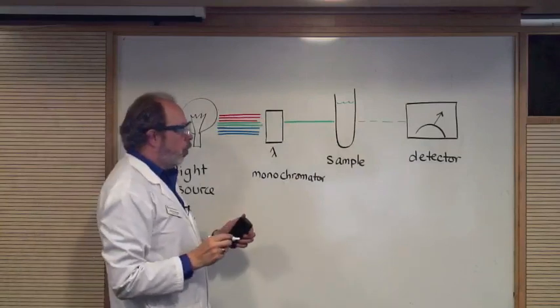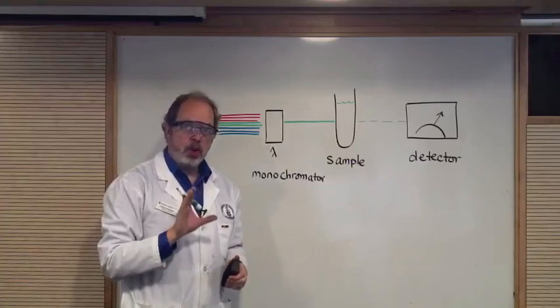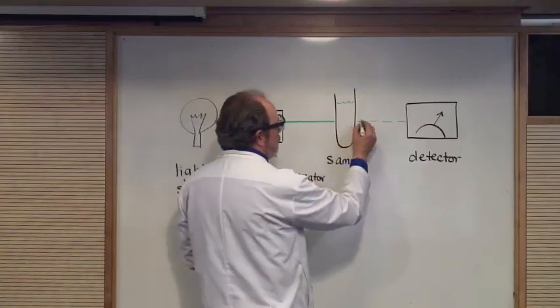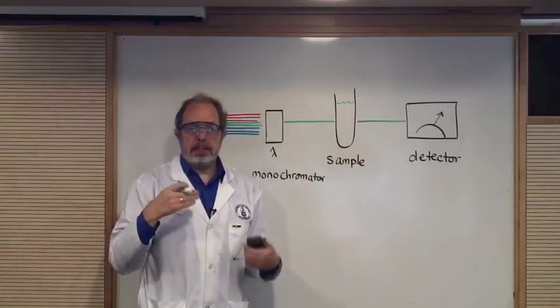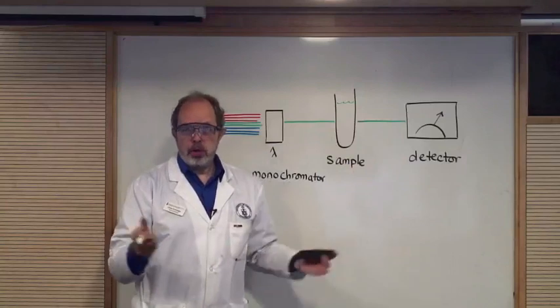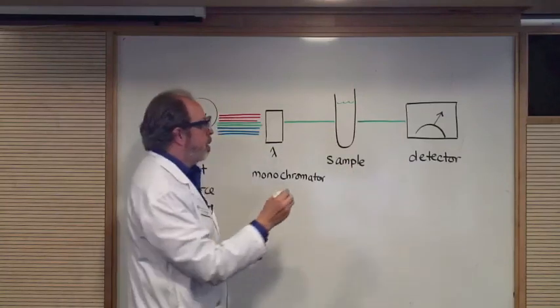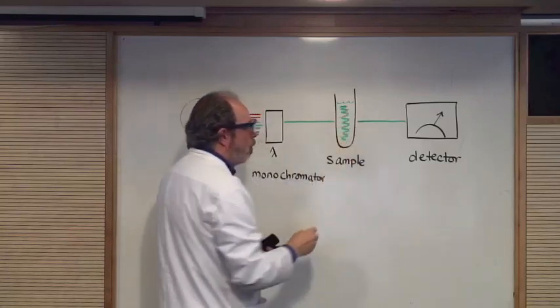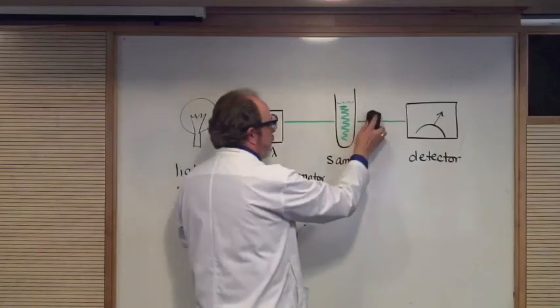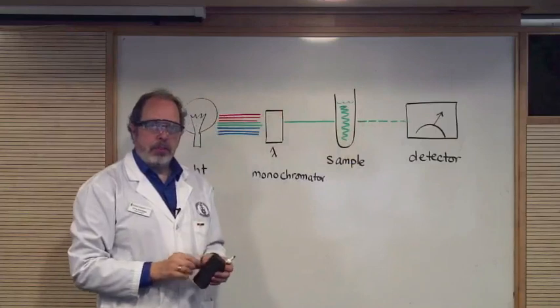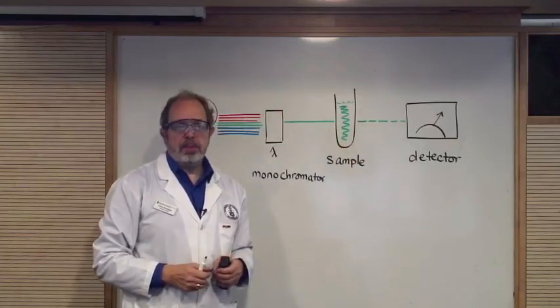Now, first of all, you put a blank solution in there. That is something that is not going to absorb any light at all, and so all of the light passes through. And you adjust the detector to say this is 100% of the light coming through, or zero absorbance. Then you can put your sample in, and I'll color this. So we've now got a sample in place, and that will absorb some light. And you're going to get slightly less light going through, and the detector will tell you how much of that light has been absorbed.